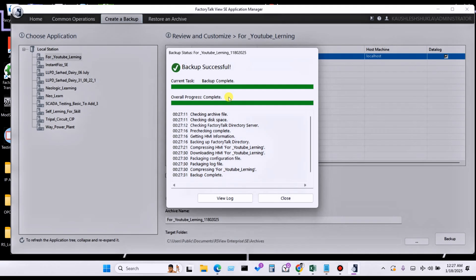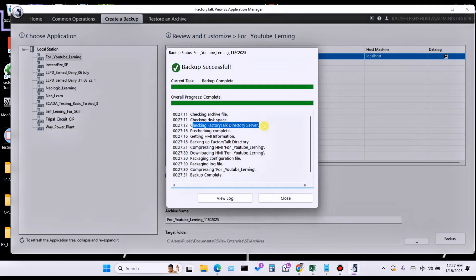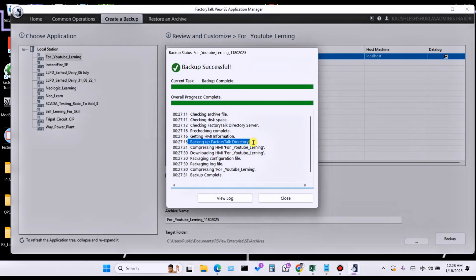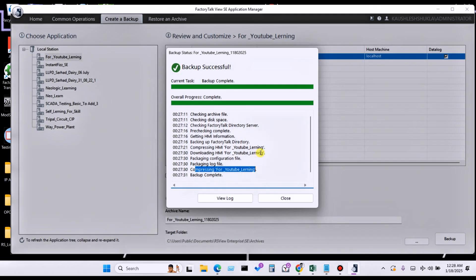The backup has been created. You can see what the software does: first it checks the archive file, then it checks disk space — whether disk space is available on this computer — then checking the FactoryTalk directory server, whether the server is available and okay. Then pre-checking is complete, getting information related to my server and my tag backup. FactoryTalk directory creates the backup, then it compresses and packages the configure file, packages the log file, and compresses the backup to reduce the file size. Then it finalizes.